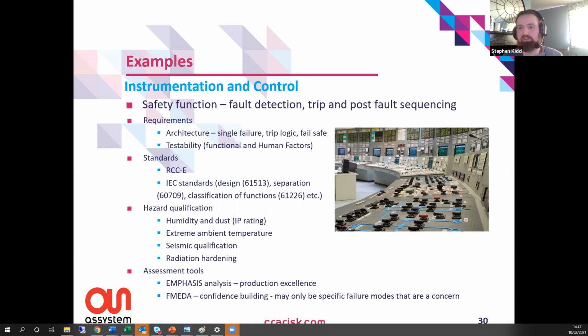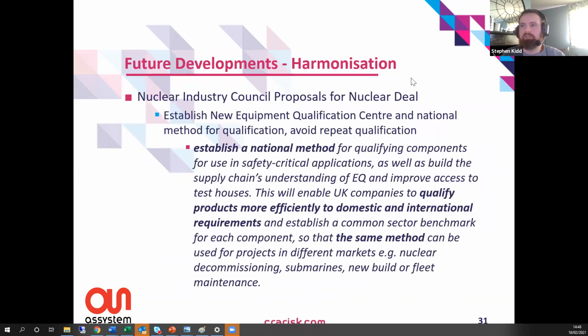There's an analysis that looks at production excellence, all the QA throughout the production, to provide confidence in the final system. Or FMEDAs and things, where it might only be a specific failure mode that we're concerned about. Therefore, licensees may ask to see the full SIL assessment and failure modes and effects analysis, not because they want to start building these things themselves, but because they want to understand the contribution a specific failure mode makes. Future developments, just the final slide.